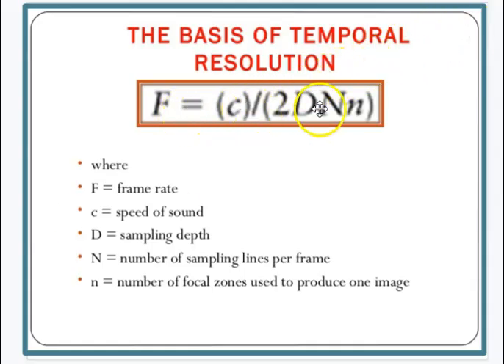The basis of temporal resolution is our formula, where F equals frame rate, C is the speed of sound, and D is the sampling depth. It's affected by depth, so we get 2 times the depth. Then the number of sampling lines per frame, and the number of focal zones used to produce an image. I don't know how many focal zones we can use. I think we can change the width of our focal zone, but I'm not sure we use more than one. I think we only use one focal zone in echo on this transducer, so I wouldn't worry too much about that. But that's the formula. You don't have to know this formula. That's basically what the machine is calculating for its algorithm.